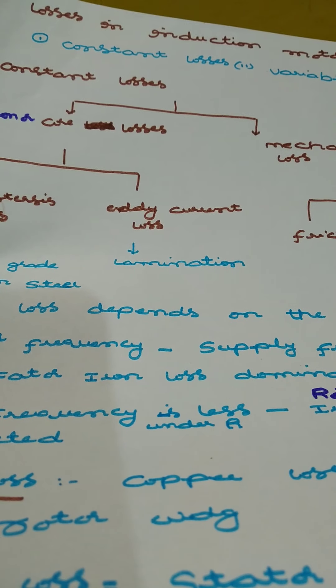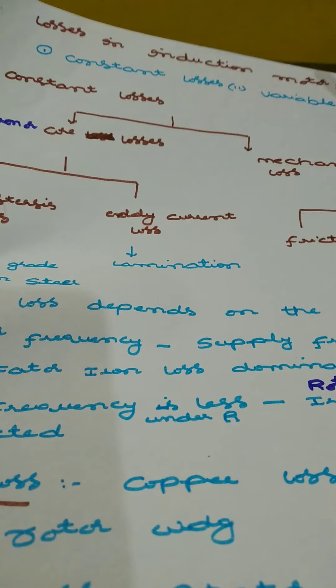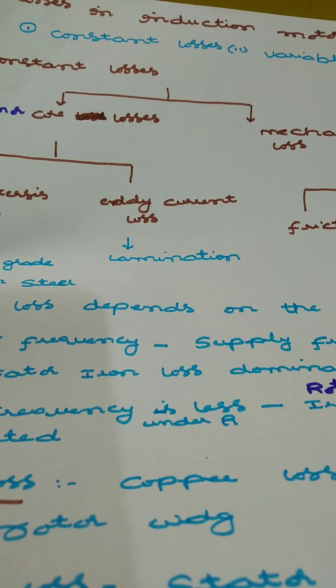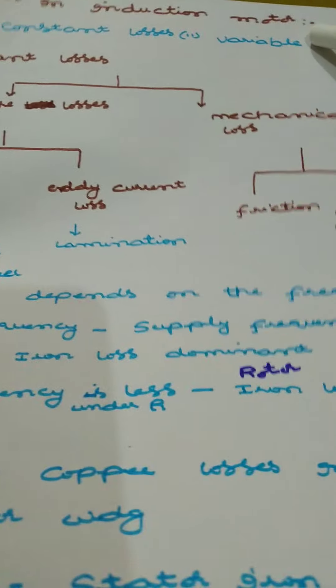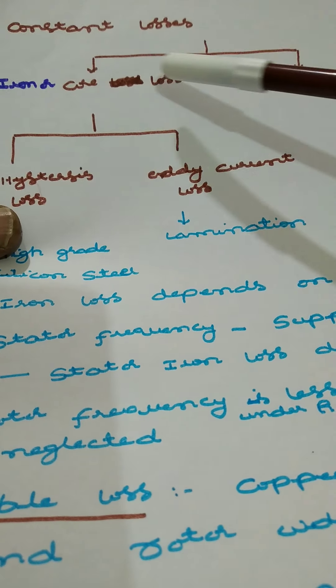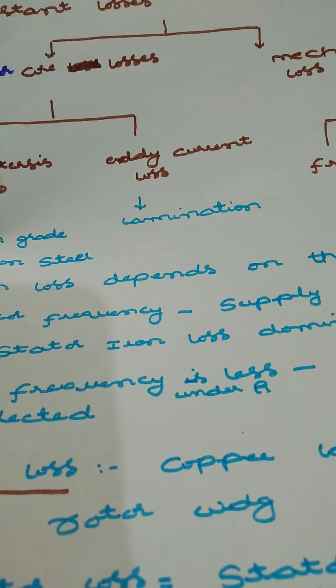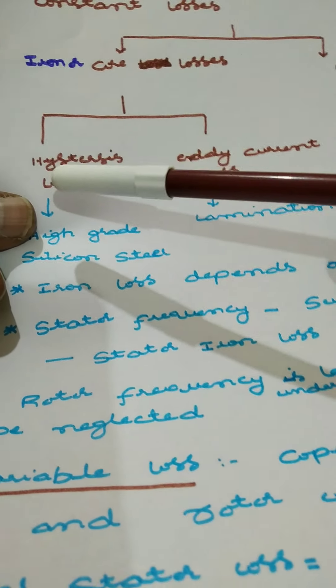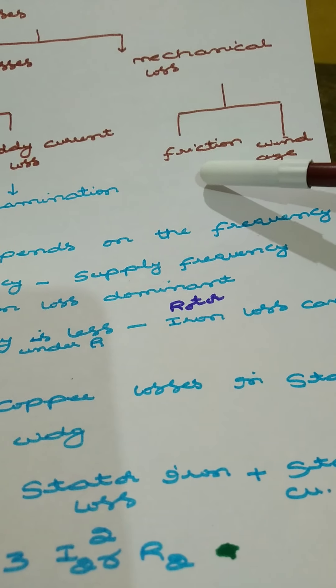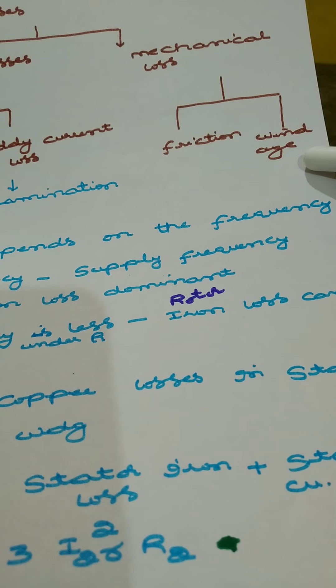Today we shall discuss losses in an induction motor. Losses can be divided into two parts: constant losses and variable losses. Constant losses can be further divided into iron or core losses and mechanical losses. Core loss can be divided into two parts: hysteresis loss and eddy current loss. Mechanical losses consist of friction losses and windage losses.